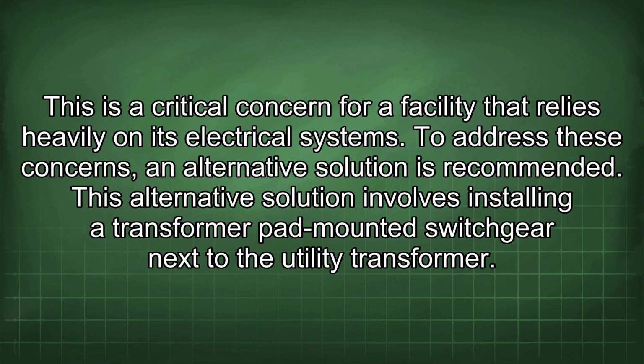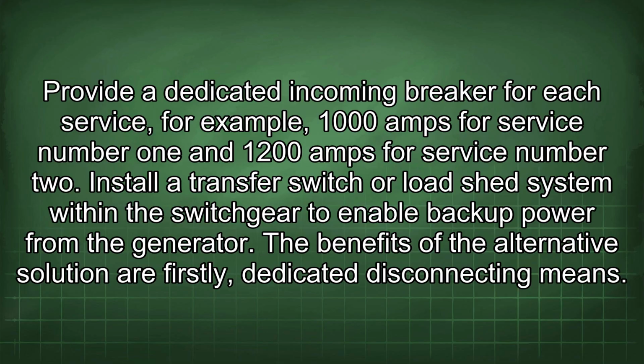To address these concerns, an alternative solution is recommended. This alternative solution involves installing a transformer pad-mounted switchgear next to the utility transformer. Provide a dedicated incoming breaker for each service, for example, 1000 amps for service number 1 and 1200 amps for service number 2. Install a transfer switch or load shed system within the switchgear to enable backup power from the generator. The benefits of the alternative solution are, firstly, dedicated disconnecting means.